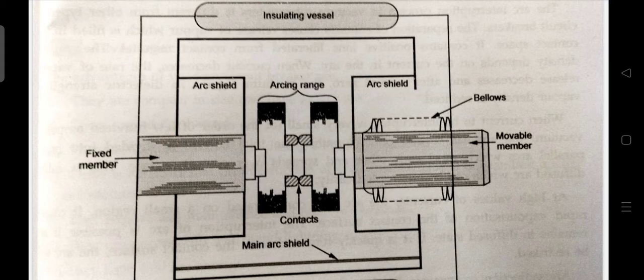The working will be when the breaker operates, the moving contact separates from the fixed contact and arc is struck between the contacts. The production of arc is due to the ionization of metal ions and depends very much upon the material of contacts. The arc is quickly extinguished because the metallic vapors, electrons and ions produced during arc are diffused in a short time and seized by the surface of moving and fixed members and shields.